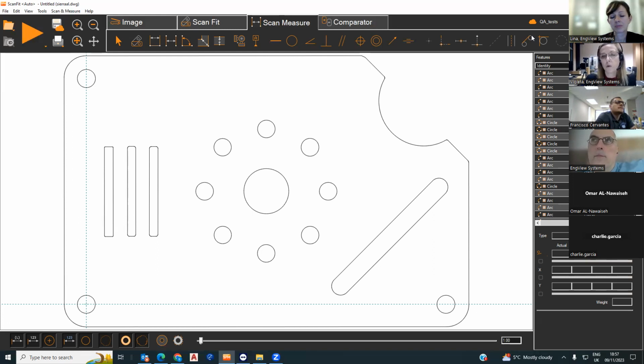No, because we generate a special, very precise contour on a pixel level only on the solid material, not on the scanner dust and small pieces. We have special parameters to remove the dust and the hairs from the scanner glass. Also, if the glass has been scratched by aluminum, it does not take effect on the measurement because the scratch is gray, the profile is black.